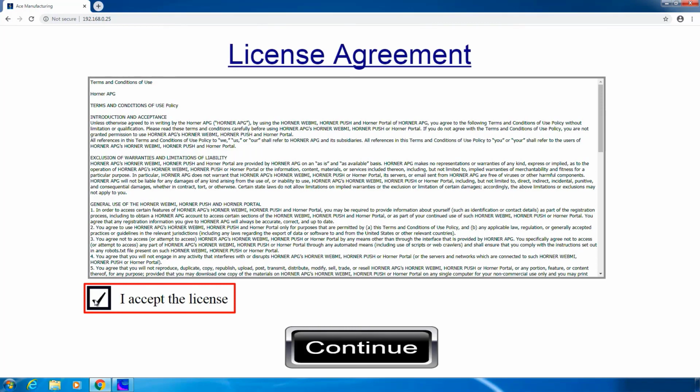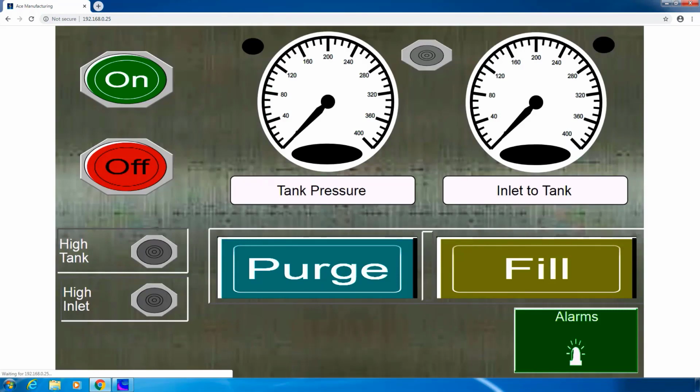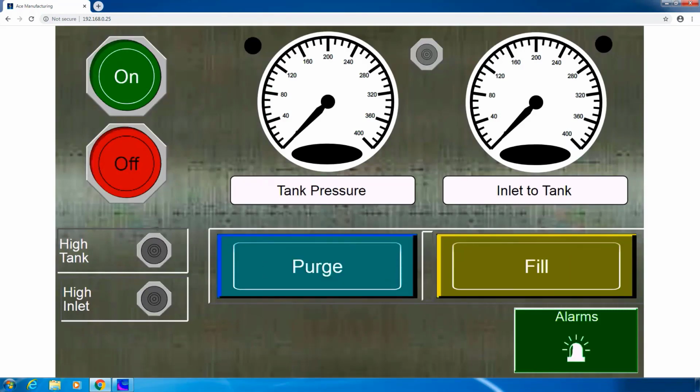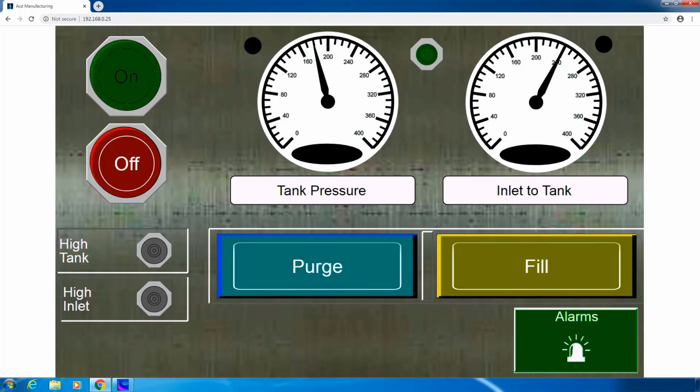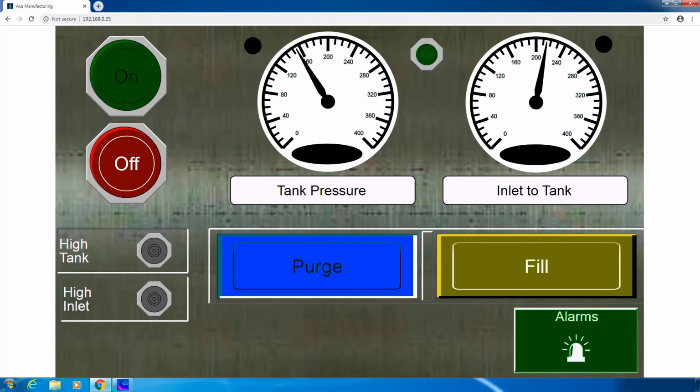So here is a real-world view of my application. So if I were to operate the OCS, I would see a clear reaction through WebMI. As you can see, there is a visible response on the screen, and this is accurately portraying my work on the OCS. So there we go. With a small few steps, we've taken an existing project with existing screens and published those as web pages using WebMI.